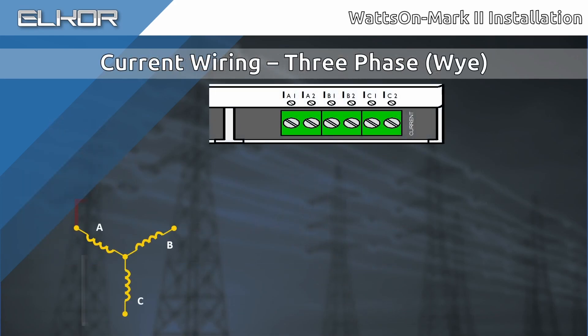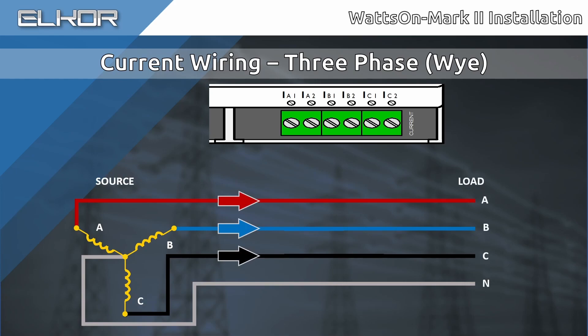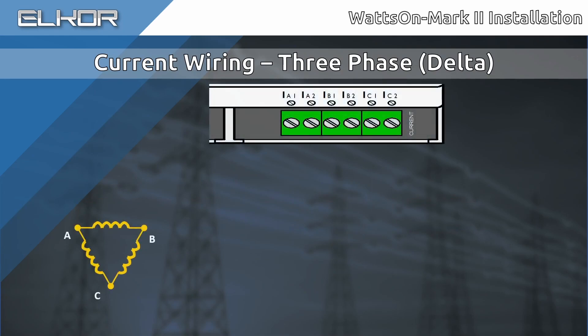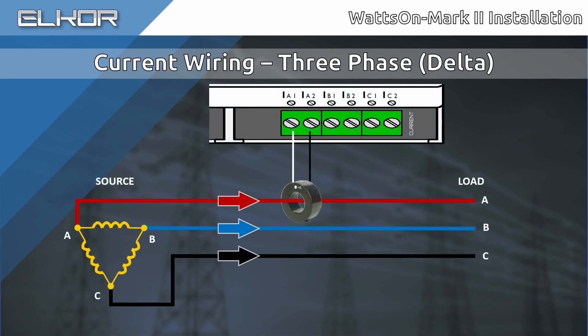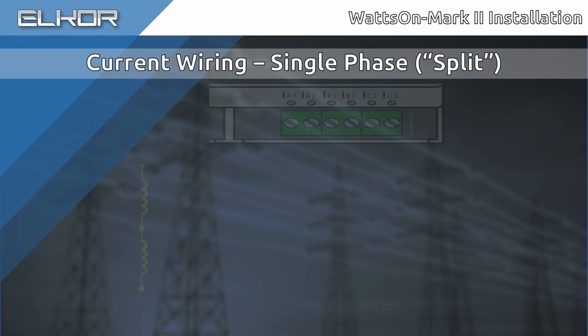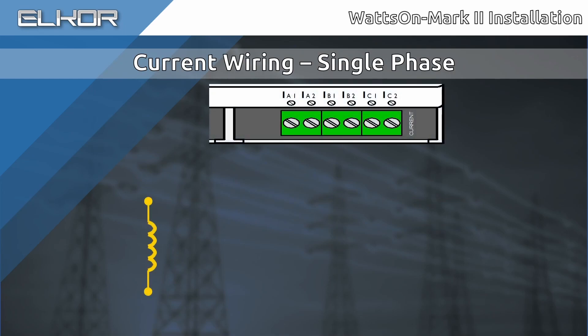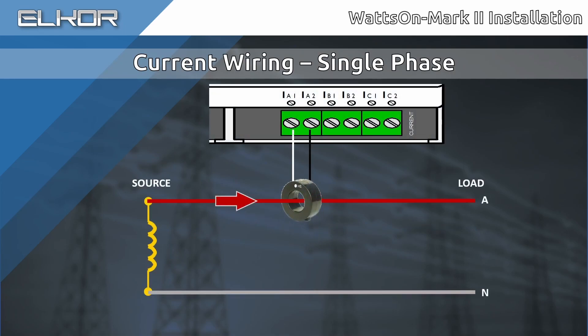As with voltages, varying wiring types require varying CT installations. For a three-phase four-wire Y system, install one CT per phase. While it is possible to use fewer CTs only when using a 5-amp meter and CTs, review the various wiring diagrams on Elkor's website for more information. For a three-wire delta, again install one CT per phase. For a split-phase system, install one CT on each phase. For a single-phase system, install one CT on the phase. As mentioned earlier, it is possible to monitor multiple single-phase loads due to the meter's ability to measure all parameters on a per-phase basis. In this case, install a CT for additional loads to be monitored.